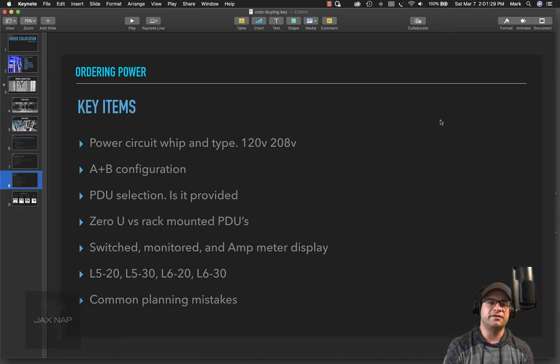Okay, when getting into the data center and you figured out the space you need, next comes ordering power. We're going to cover a couple of key items that are important when considering the type of power you're going to be ordering. Number one, is the power circuit whip you're ordering going to be 120 volts or 208 volts? Is it going to be coming in A and B configuration? Is the PDU selection that important to you?